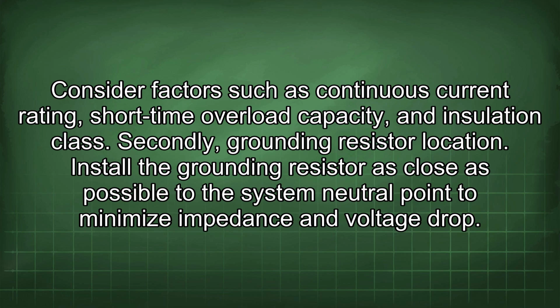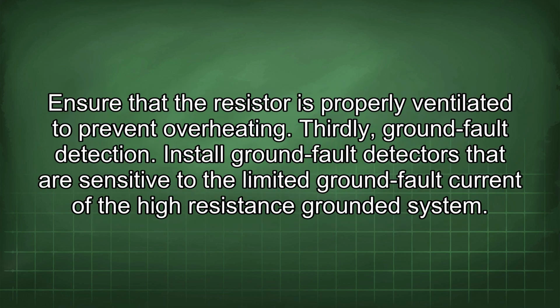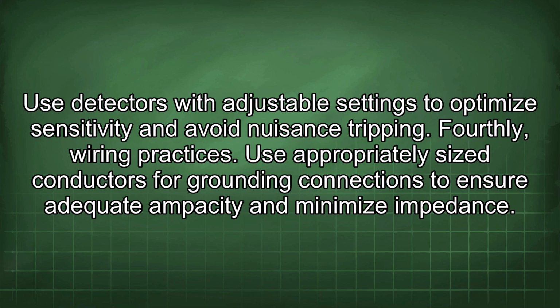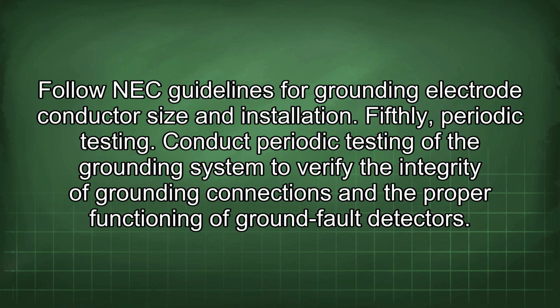Secondly, grounding resistor location. Install the grounding resistor as close as possible to the system neutral point to minimize impedance and voltage drop. Ensure that the resistor is properly ventilated to prevent overheating. Thirdly, ground fault detection. Install ground fault detectors that are sensitive to the limited ground fault current of the high-resistance grounded system. Use detectors with adjustable settings to optimize sensitivity and avoid nuisance tripping. Fourthly, wiring practices. Use appropriately sized conductors for grounding connections to ensure adequate ampacity and minimize impedance. Follow NEC guidelines for grounding electrode conductor size and installation.